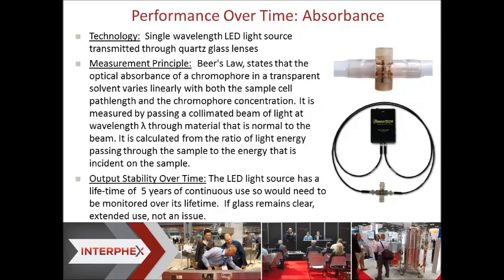And the light source has a lifetime of 5 years continuous use or more. And as long as the glass remains clear and doesn't interfere with and create any false absorption, it can be used over long periods of time. So if the glass is compatible with the sample, it doesn't degrade, that could be used over long periods of time.